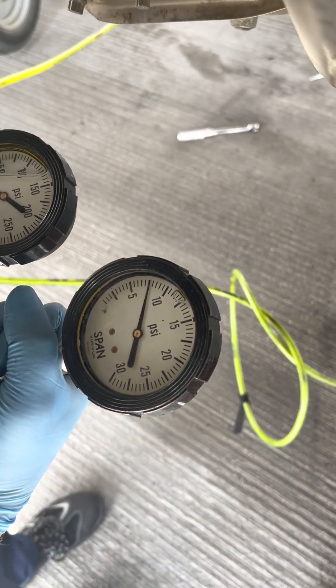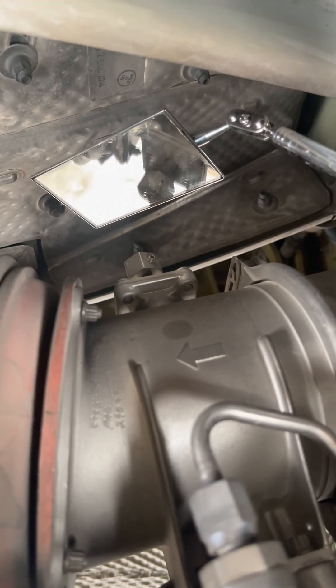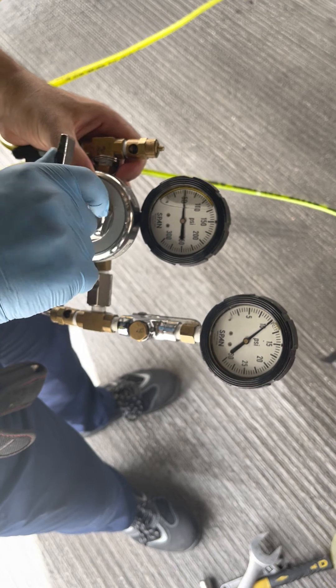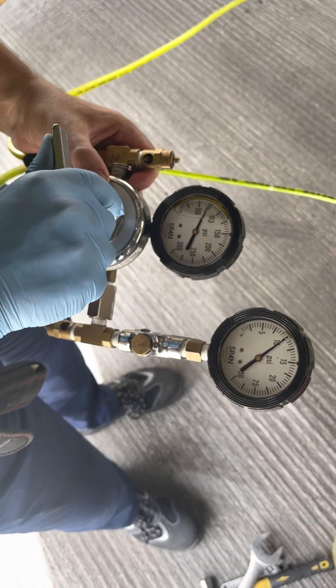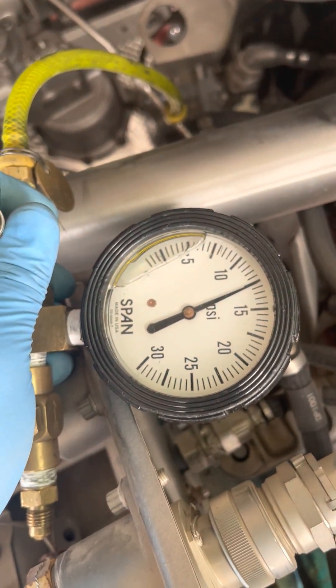What pressure are we at? We are at 7.5 psi. Now let us go a little more. It's fully closed. Okay, keep going until 7.0 to 7.5. We are at 7.5 psi, and at this stage our control pressure is around 12.5 psi.